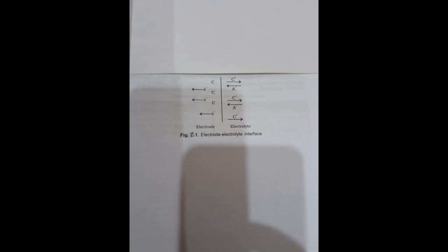Therefore, electrodes must have the capability of conducting a current across the interface between the electronic measuring circuit and the body. The electrode actually carries out a transducing function, where current flows in the body by ions, along with the current flow in the electrode by electrons.